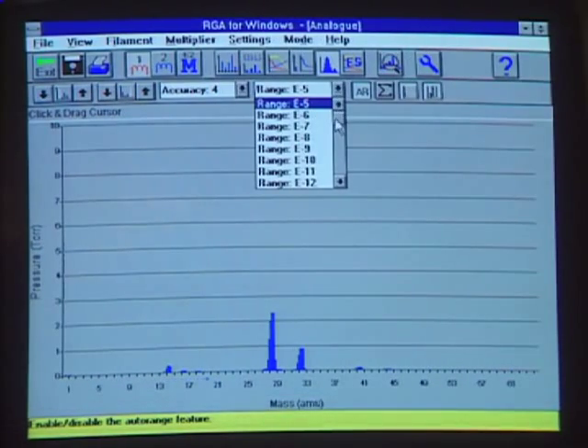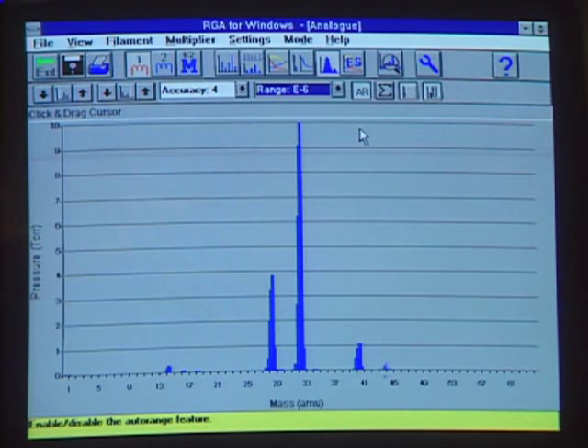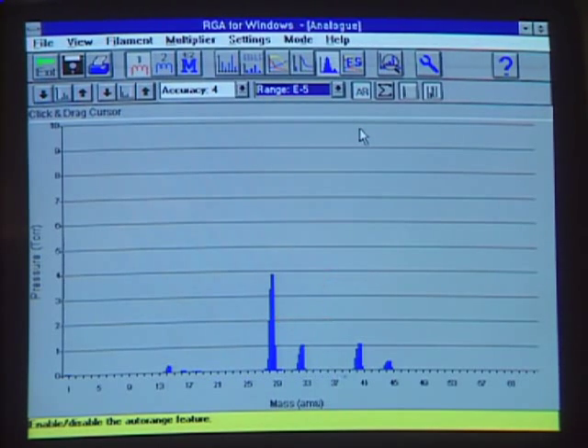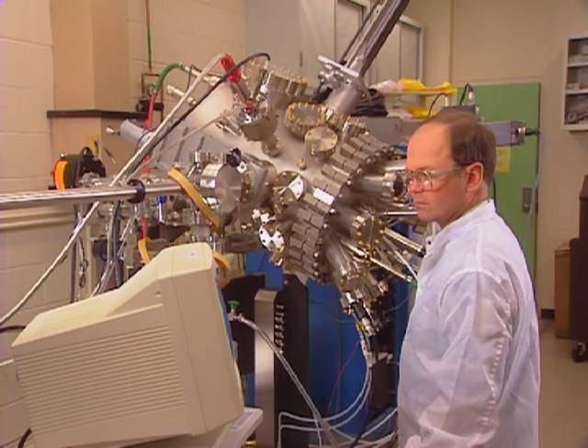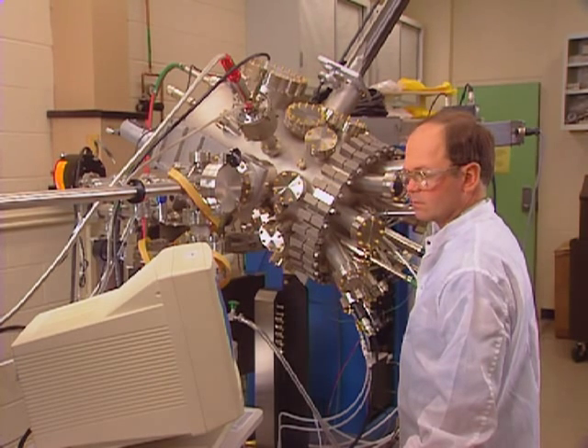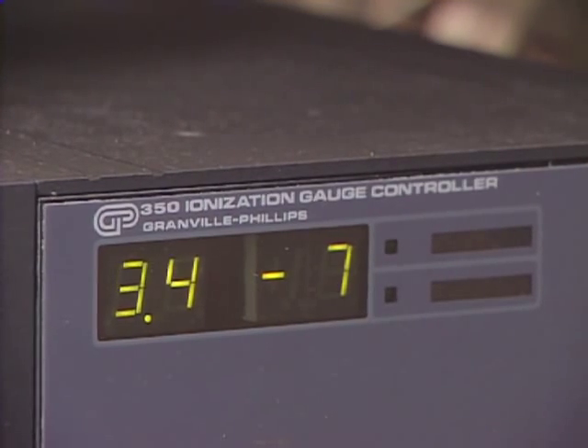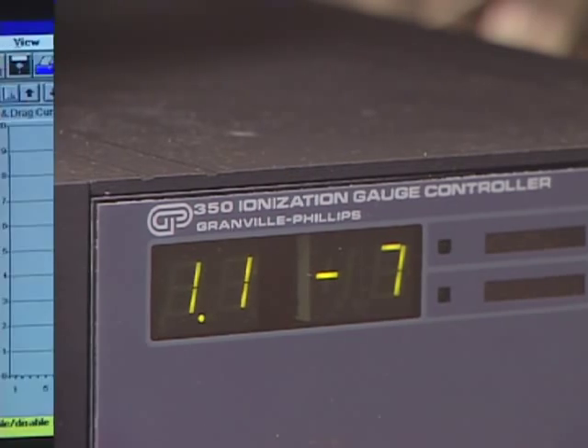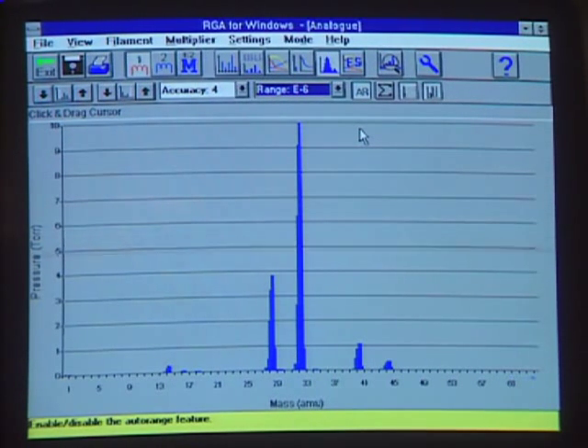In addition, the residual gas analyzer reveals that the system shows unusually high concentrations of molecular oxygen and molecular nitrogen — the major gas species in the atmosphere. This indicates that atmosphere may be leaking into the system. It appears that we have a vacuum leak. Measuring the pump-down time of the system will supply more evidence. An analysis of the residual gases present can not only indicate whether a leak is present, but also help us determine what type of leak we have.